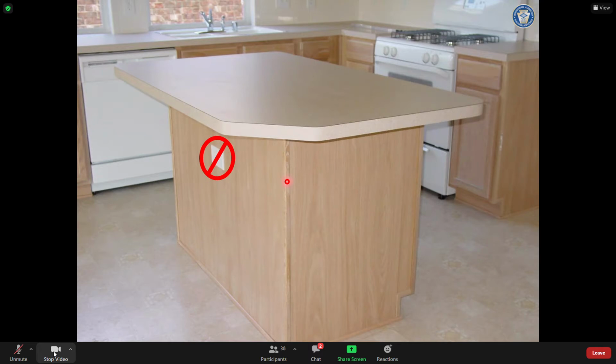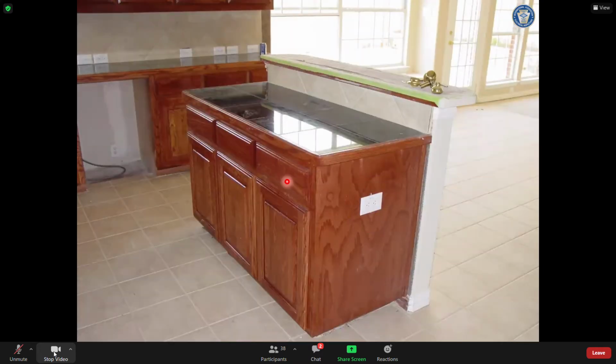Yeah, Keith, can I jump in on that for a sec? Sure, sure. So along these lines, I dealt with this one on some high-rise construction. So we're talking about this condition times 300. And what we did, because the code does not say it can't be there, but we had the 10-inch overhang, we had them put the receptacles in per the code. And obviously, they didn't want to remove those because of the costs associated with it. So we urged them, since the unsafe condition would still exist. That was a great word you used, urged.